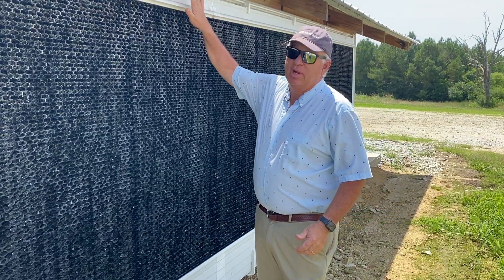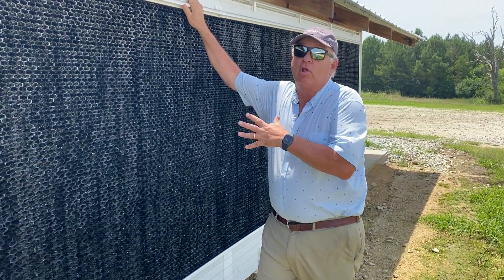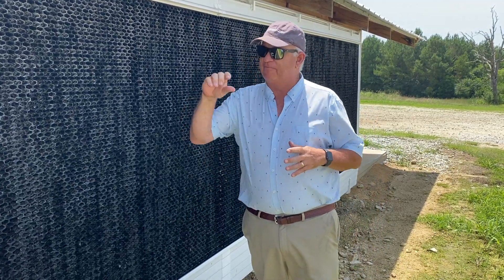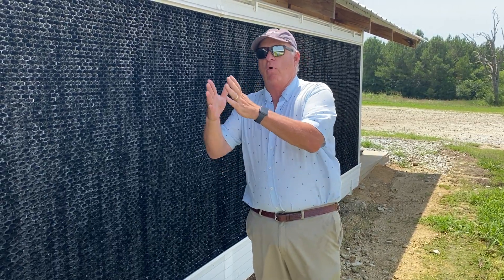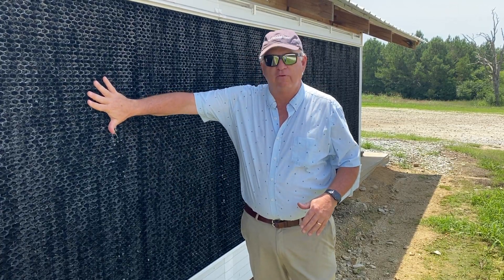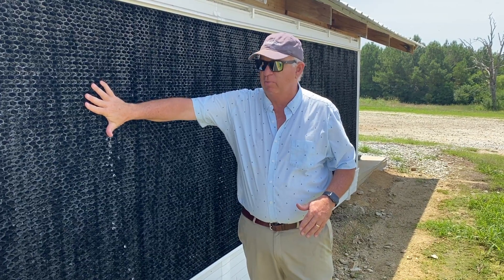In part, it has a really good header on this system. This isn't the only type — there are other systems you can use. But the question is: can you run your pump full out, not cutting back the flow, and be able to keep the water on the pad like it is here? Again, really a lot of water flow there — that is just flowing off my finger right there, which is ideal.